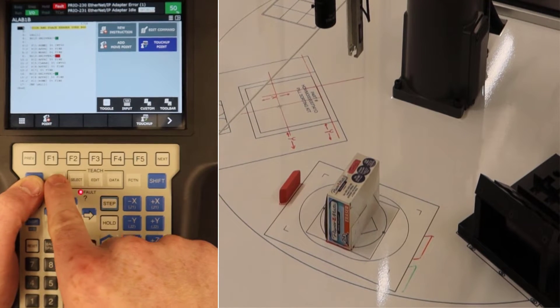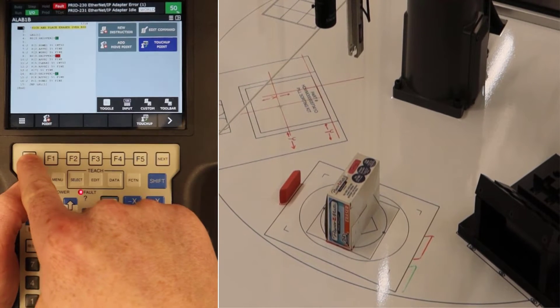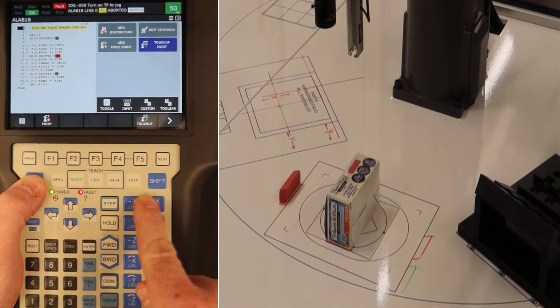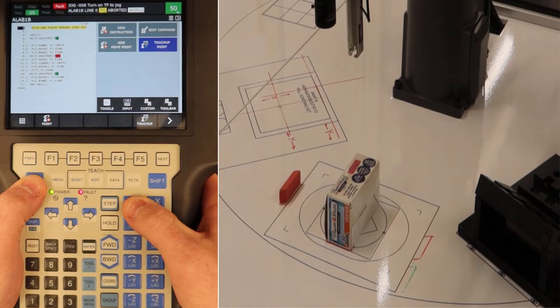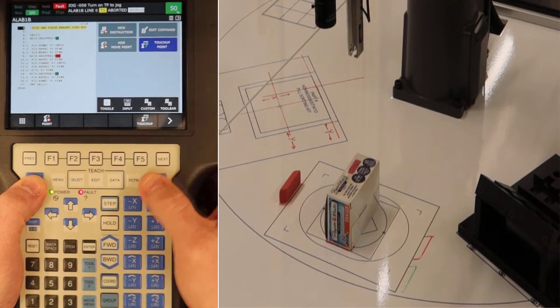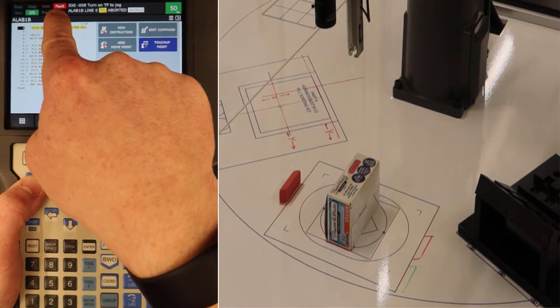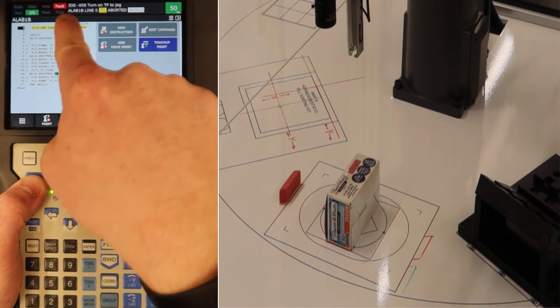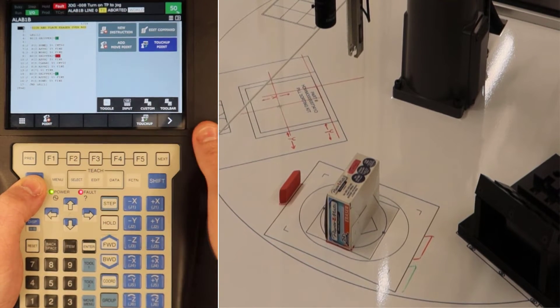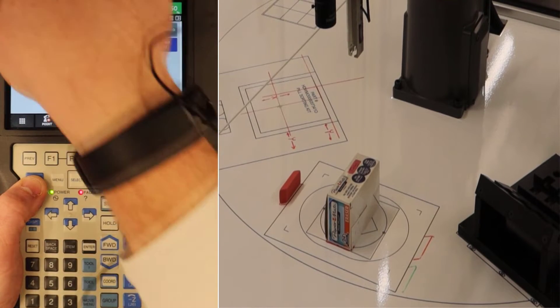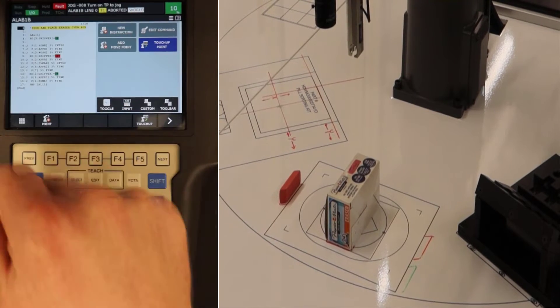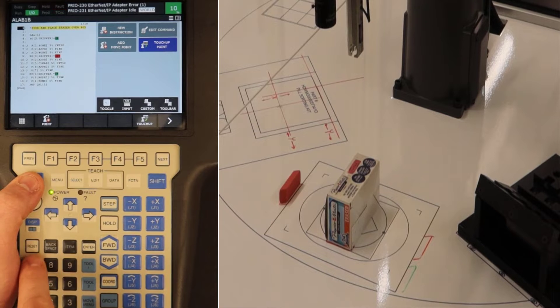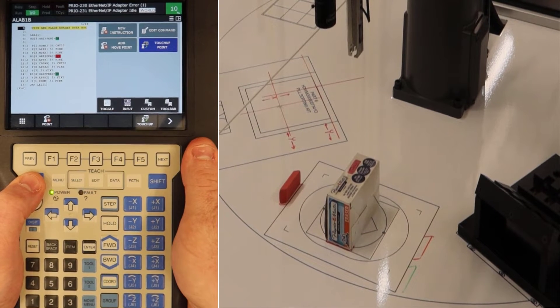We can still work the teach pendant, we can still navigate menus, but we can't move the robot and it's going to give me that error status. So whenever you're running into issues with the robot, definitely make sure to look at your fault indicator and what type of message you're getting from the top of the teach pendant. Turning it on and then hitting reset will quickly resolve that.